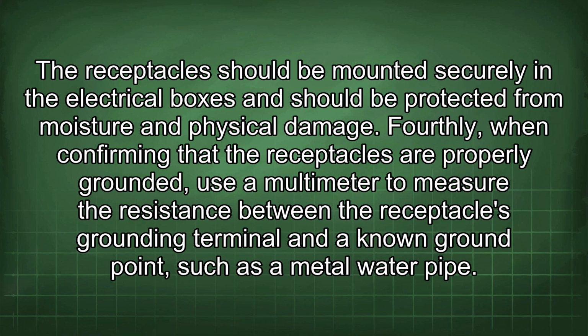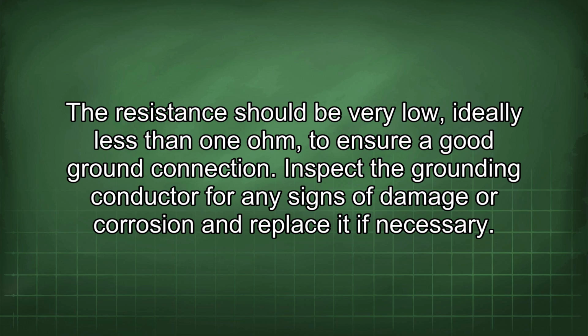Fourthly, when confirming that the receptacles are properly grounded, use a multimeter to measure the resistance between the receptacle's grounding terminal and a known ground point, such as a metal water pipe. The resistance should be very low, ideally less than 1 ohm, to ensure a good ground connection. Inspect the grounding conductor for any signs of damage or corrosion and replace it if necessary.